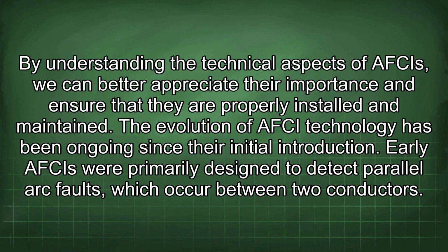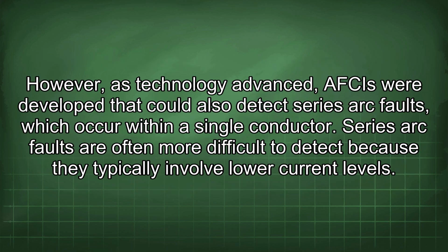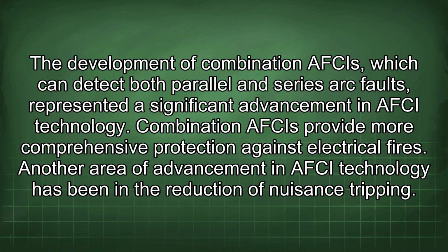The evolution of AFCI technology has been ongoing since their initial introduction. Early AFCIs were primarily designed to detect parallel arc faults, which occur between two conductors. However, as technology advanced, AFCIs were developed that could also detect series arc faults, which occur within a single conductor. Series arc faults are often more difficult to detect because they typically involve lower current levels. The development of combination AFCIs, which can detect both parallel and series arc faults, represented a significant advancement in AFCI technology. Combination AFCIs provide more comprehensive protection against electrical fires.